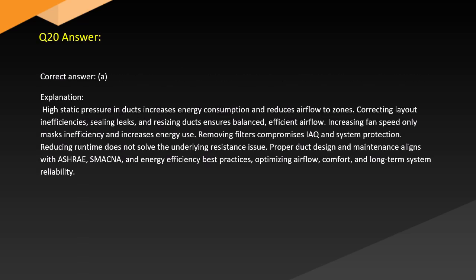Answer. Correct answer: A. Explanation. High static pressure in ducts increases energy consumption and reduces airflow to zones. Correcting layout inefficiencies, sealing leaks, and resizing ducts ensures balanced, efficient airflow. Increasing fan speed only masks inefficiency and increases energy use. Removing filters compromises system protection. Reducing runtime does not solve the underlying resistance issue. Proper duct design and maintenance align with ASHRAE, SMACNA, and energy efficiency best practices, optimizing airflow, comfort, and long-term system reliability.